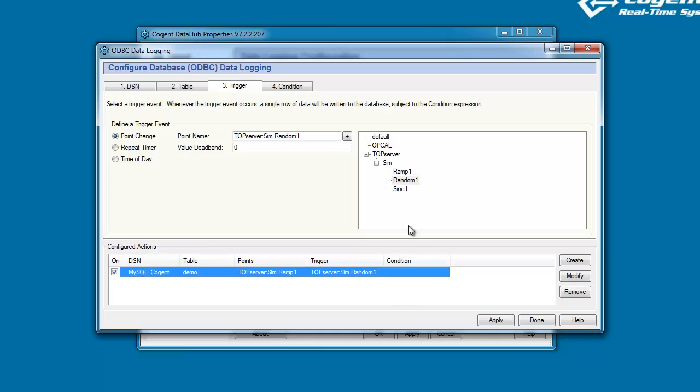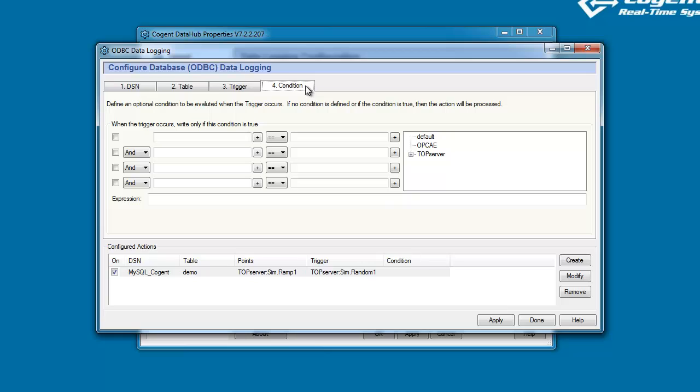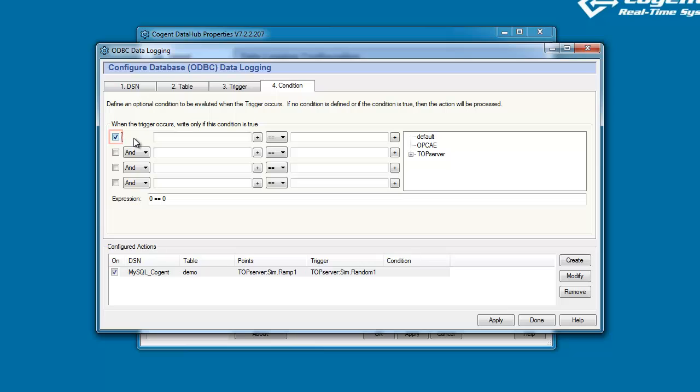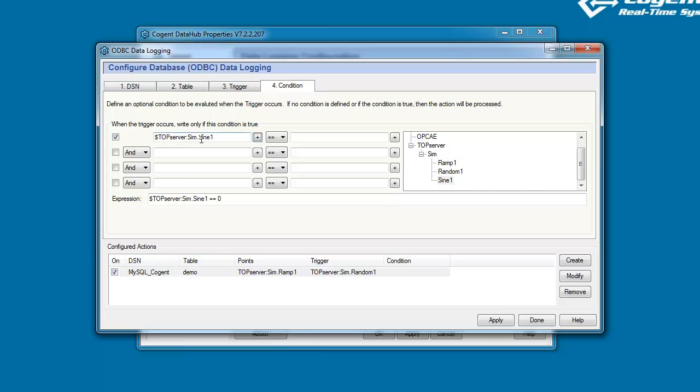But I want to show you how we can configure a condition statement. Condition statements are evaluated every time the Data Hub trigger event fires, and the database will only get a new value, the Data Hub will only write to the database, if the condition statement is true when the trigger event fires. So as an example, I'm going to set up a trigger event and say that I want to write new values for Ramp1. Every time the trigger event fires, I'm going to evaluate the value of Sine1, and write to the database if Sine1 is greater than 35.